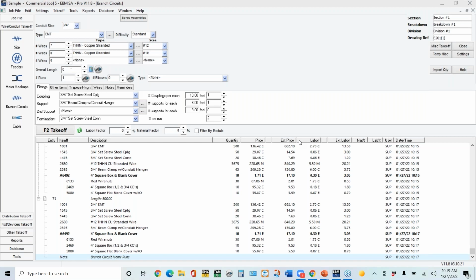There's another question about understanding the adjustment for the formula. The adjustment to the formula is really to justify that it's going to come out to 15 to 20 feet. If you do the math and it says that the average length between each point is 10 feet, then you would have to adjust for switches by 5 to 7 feet, because that gives you the vertical distance.